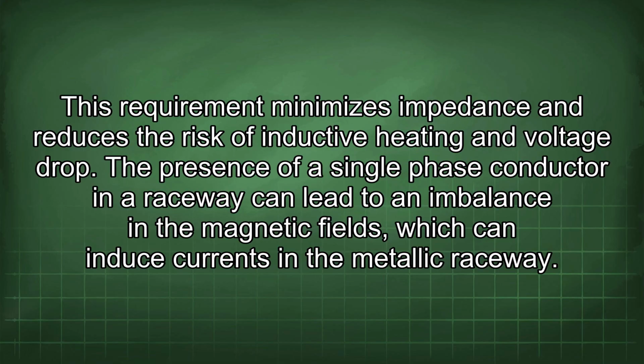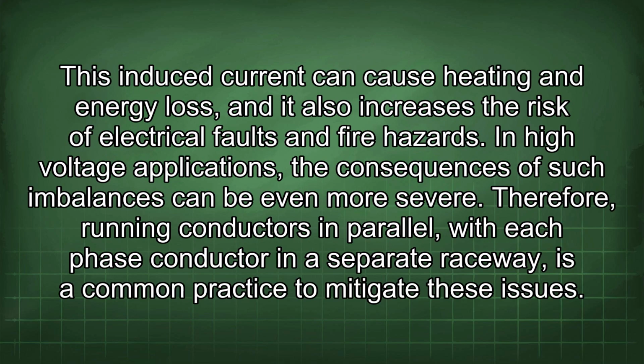The presence of a single-phase conductor in a raceway can lead to an imbalance in the magnetic fields, which can induce currents in the metallic raceway. This induced current can cause heating and energy loss, and it also increases the risk of electrical faults and fire hazards. In high-voltage applications, the consequences of such imbalances can be even more severe. Therefore, running conductors in parallel with each phase conductor in a separate raceway is a common practice to mitigate these issues.